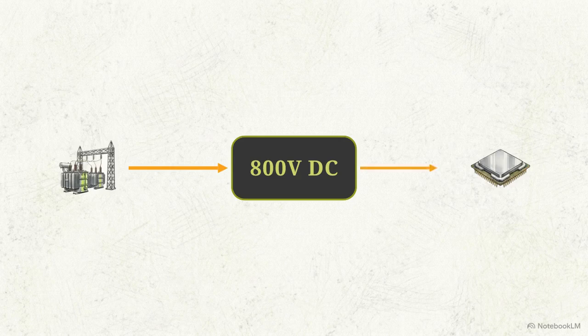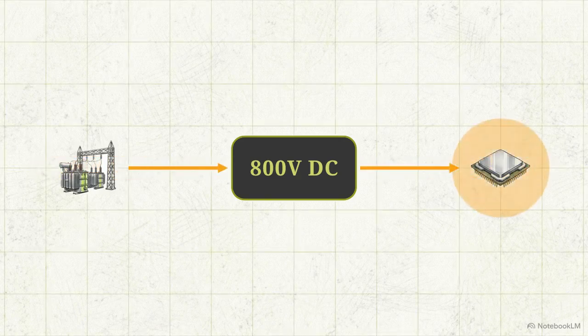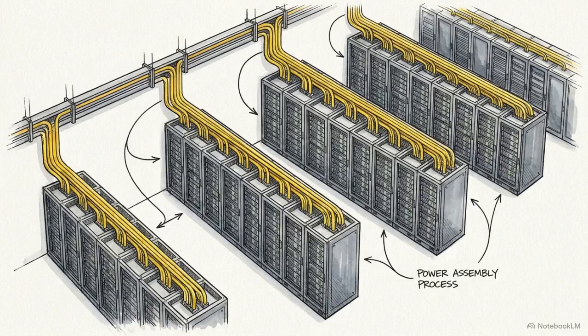The 2027 solution skips the middleman. We cut the conversion stages in half, taking power from the medium voltage grid directly to 800 volts DC and distributing it straight to the rack. This architecture shift rewrites the data center power layer to keep AI scaling functional.